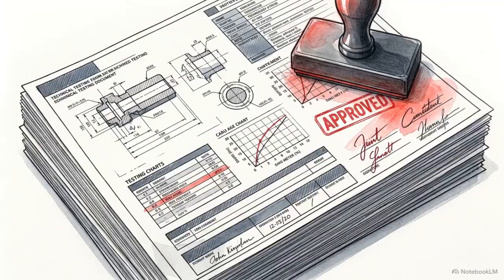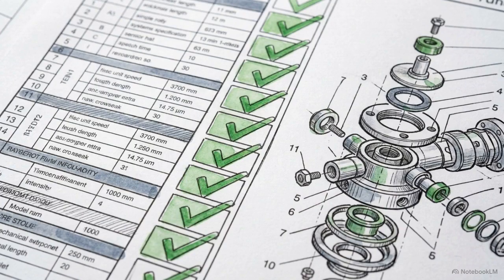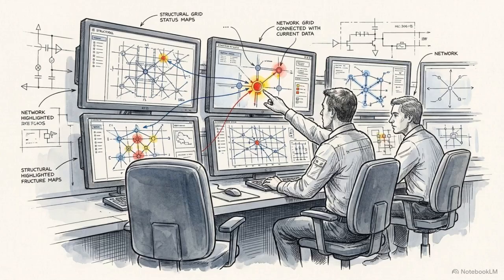Test leads are removed, and temporary grounding is cleared. The final evidence package is compiled. This includes all 16 steps of documentation, from the initial mechanical checks and IR sheets to the final tan delta and neutral unbalance reports. The final hold point requires operations and commissioning witnesses to confirm the relay resets and SCADA status before the bank is handed over for service.